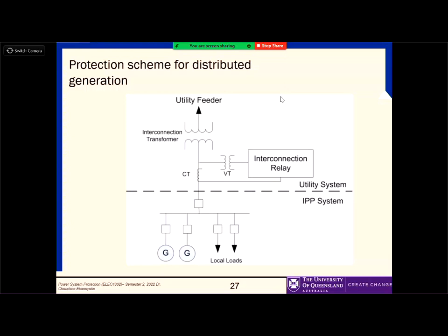But keep in mind that in the distribution protection scheme you may have generators connected to the feeder, but the feeder is traditionally fed through these sort of transformers, right? So this is the utility feeder. The power comes through this transformer and then goes into these loads. But now the difference is that the power is not only coming through this feeder; sometimes it could go from these generators to these loads. So you need some sort of protection schemes for these generators, and sometimes you may even have to change hardware.